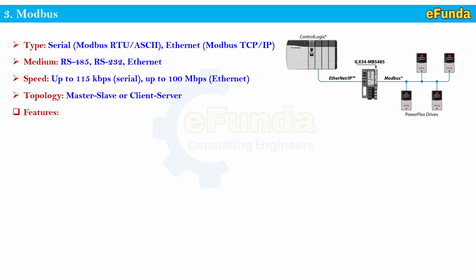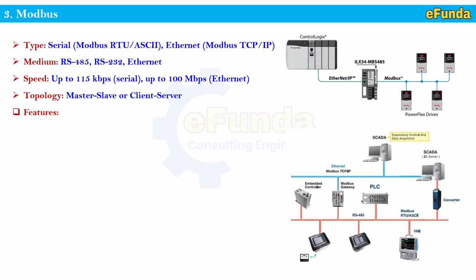Features: one can refer to the second figure where the architecture is shown, where the supervisory control and data acquisition system is connected through Ethernet Modbus TCP/IP, and then further through RS485 as well as Modbus RTU and ASCII serial types, and this will help to connect the SCADA IO server to the SCADA system. First, simple and open protocol.